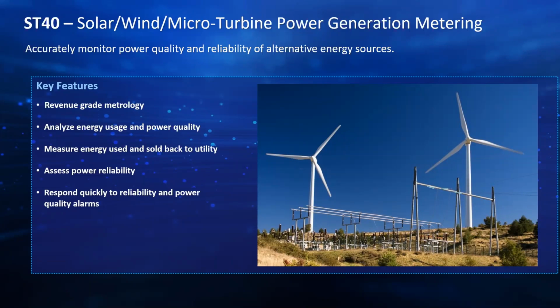Also for wind and solar, if there are any sort of harmonics that are being generated on this, we'll see this. The meter will also give you your VAR generation or consumption if you are requiring VARs to get the motor spinning on the turbines. If you have a solar application where the inverters can generate VARs, this meter will also record VARs being generated from your solar.